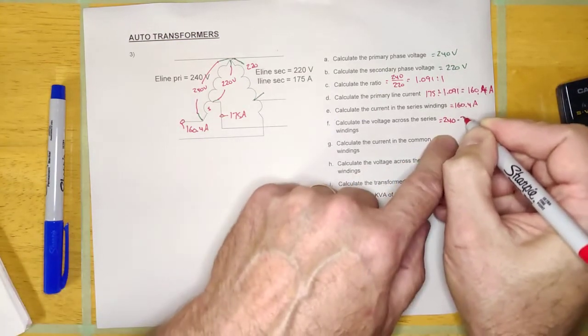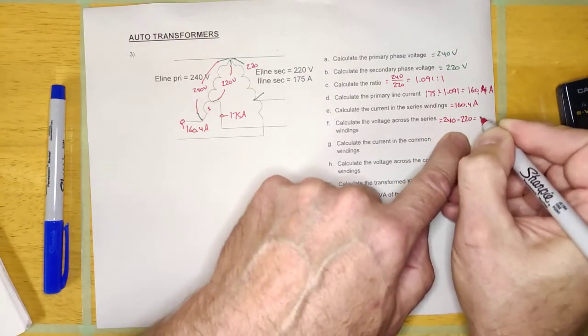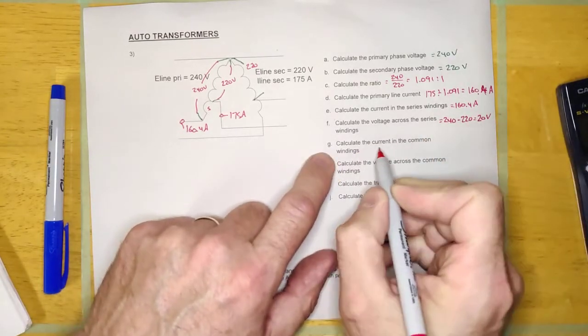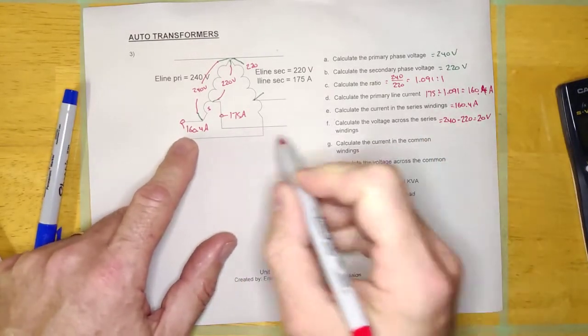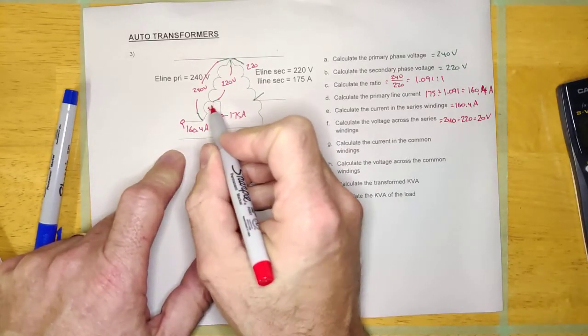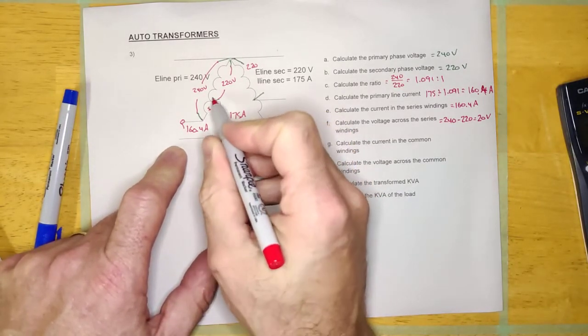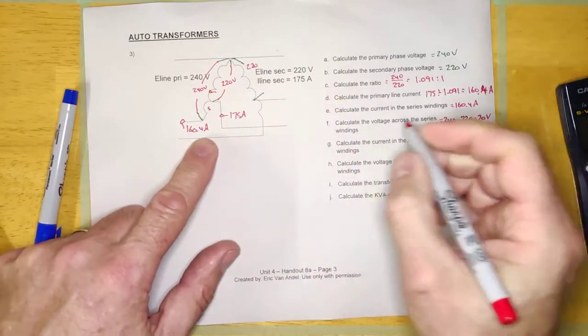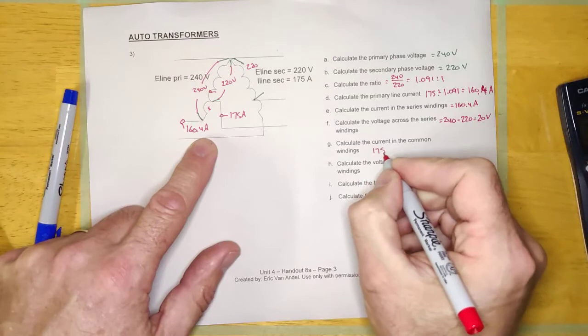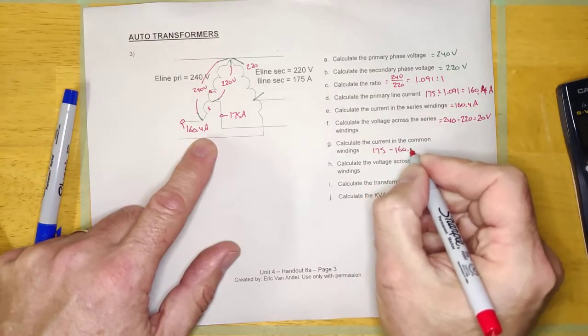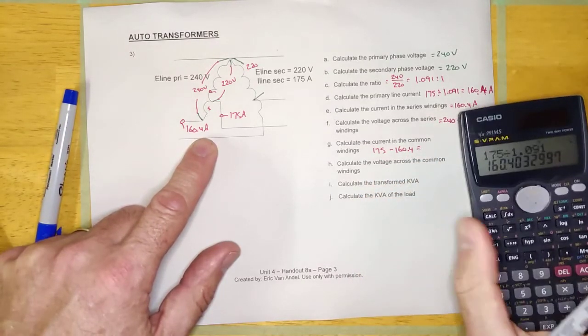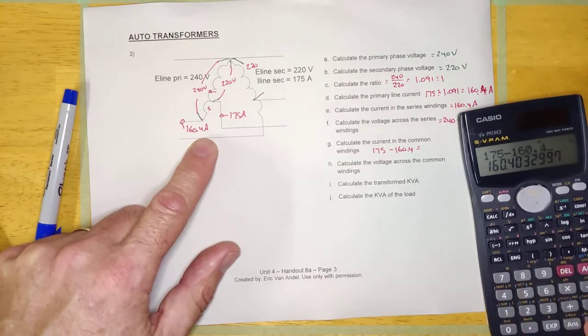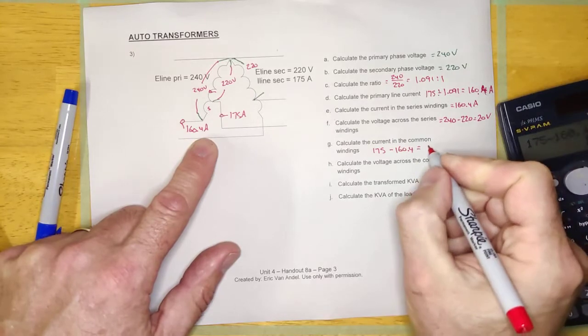Calculate the current in the common winding. Kirchhoff's law - I've got 160 amps in, 175 amps out. I'm asking about this current right here, the common current. It's going to be equal to 175 minus 160.4. 175 minus 160.4 equals 14.6 amps.